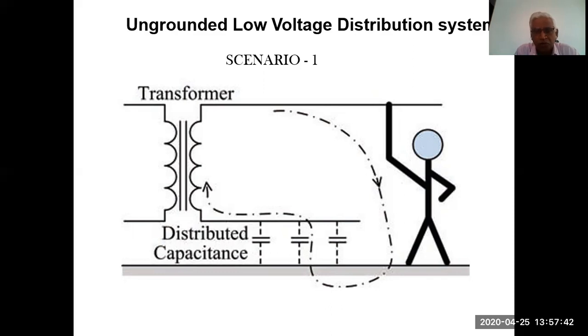Now it is shown that one person is holding one of the phases and standing on the ground, but the transformer is not earthed. You can see the direction of the current flowing. Current is flowing through his body and through the distributed capacitance and back to the neutral. As the current is flowing through his body, he should get a shock, but the shock depends on how much current is flowing. If the leakage current is something like 5 milliamperes going through the body, he may not get a shock at all.